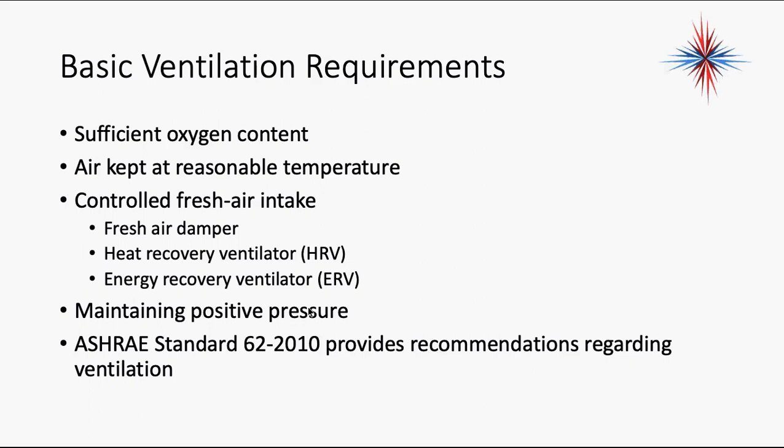If you walk into a building and the air gets pulled in as you open that door, in other words, you feel it on the back of your neck where the air is being pulled into the building, that building is in a negative pressure. That means that we do not have proper insulation or ventilation in that building, and something is leaking air out of that building. Nine out of ten times it's ductwork in the attics or basements. But again, we want to maintain all buildings in what we call a positive pressure.